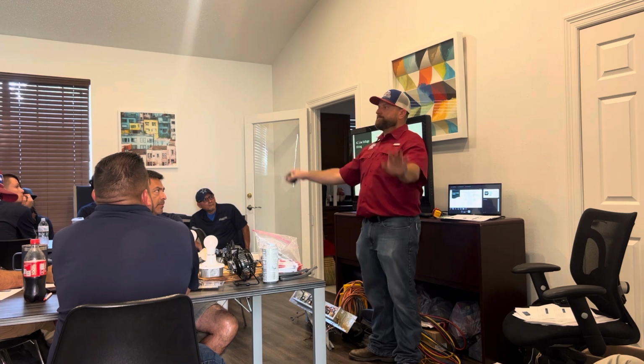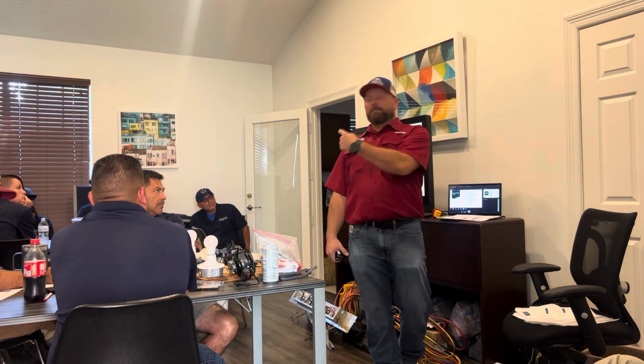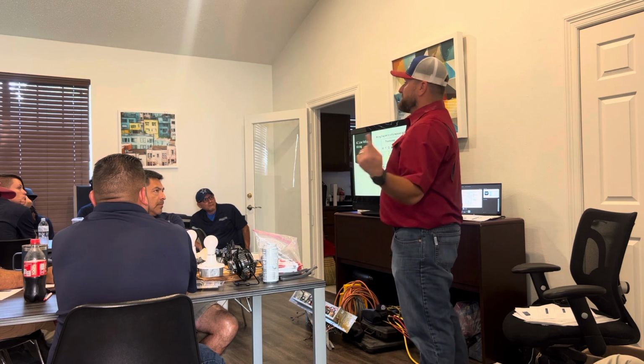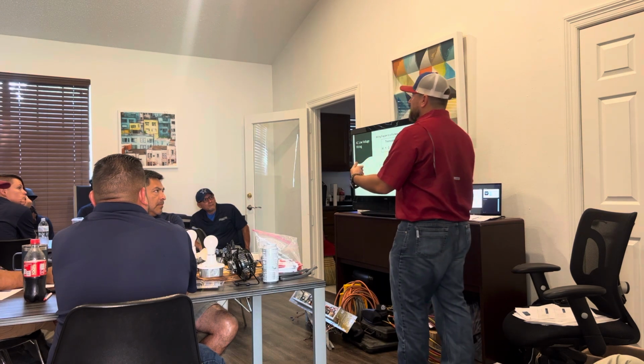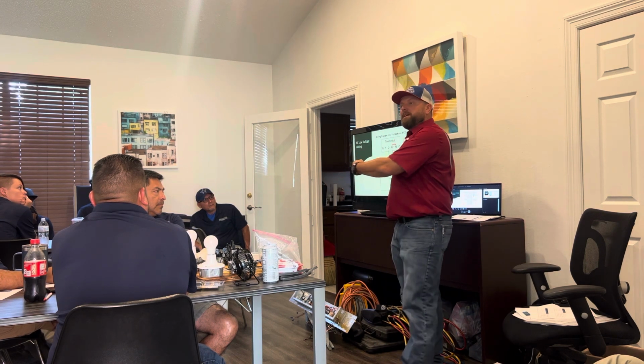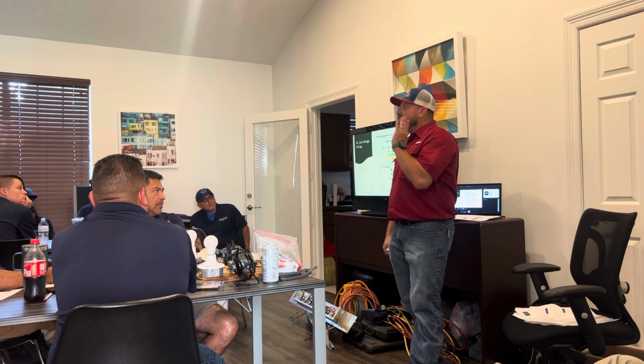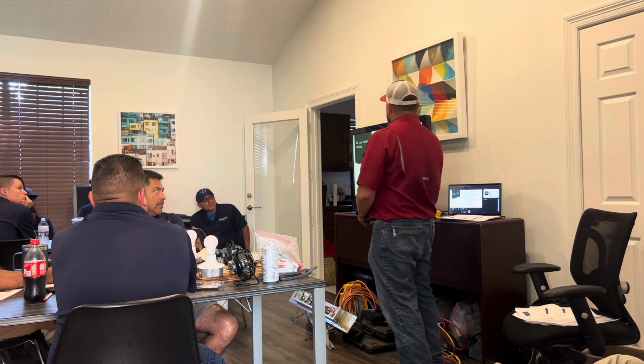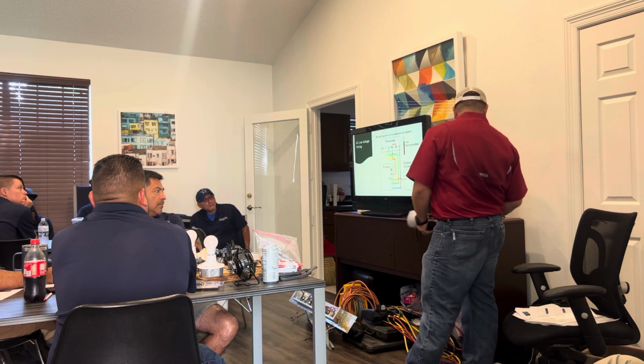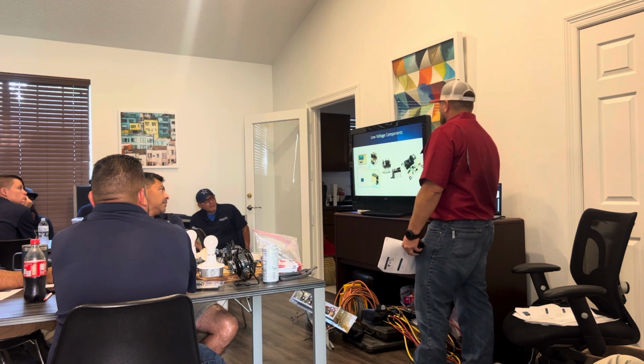It's just orchestrating that low voltage, making the connection from that R, 24 volts, over to the yellow internally in that thermostat. And it does the same thing to the fan, telling it to come on by sending 24 volts. That's why you have to make sure this transformer is 24 volts and up.